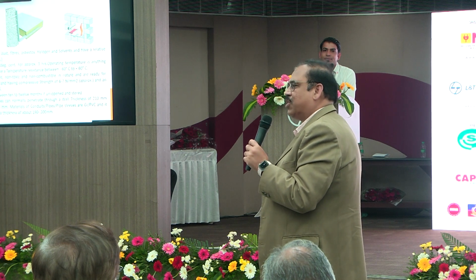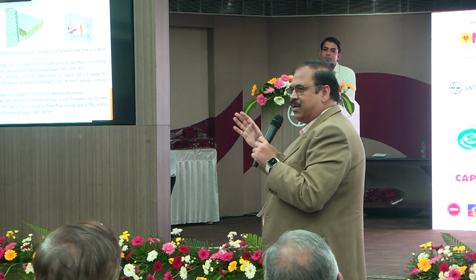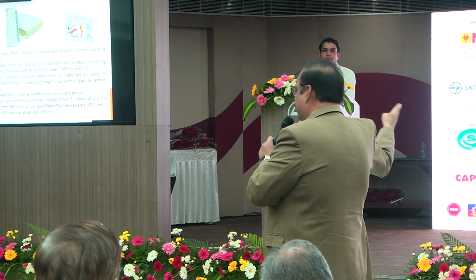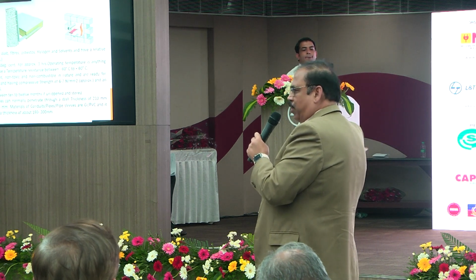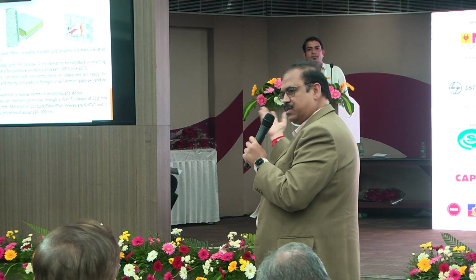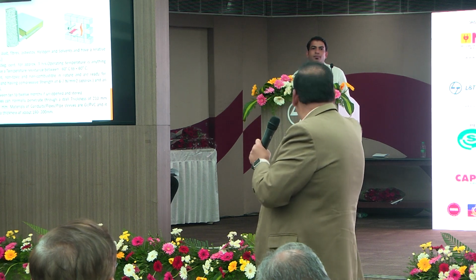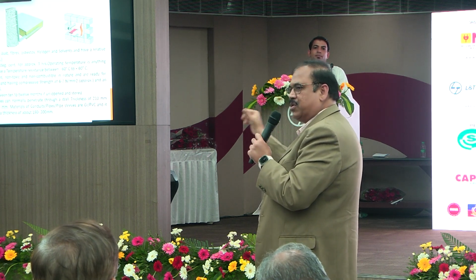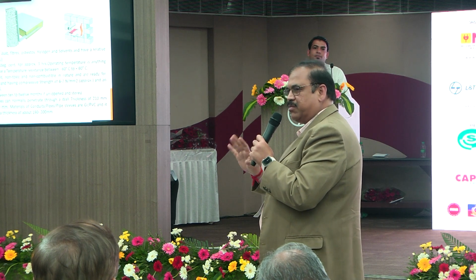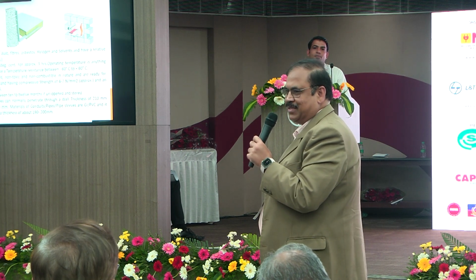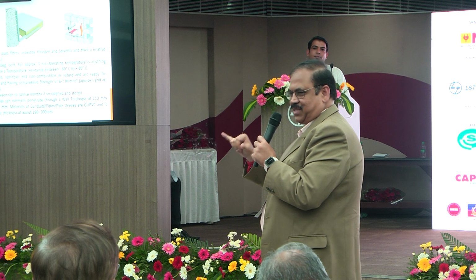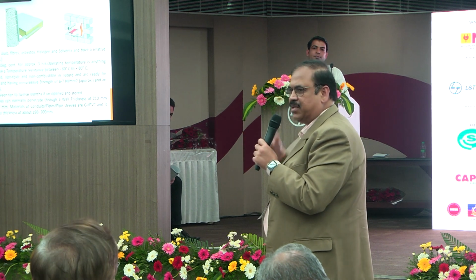Okay. So it is not compulsory to apply fully, but wherever it is changing compartmentalization, say outside ambient is open air condition but that wall is 4-hour rated, on either side of the wall it should be coated. So it should withstand for 4 hours. That is the idea of this coating.